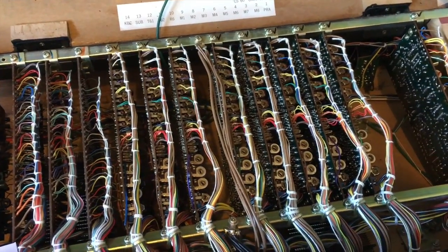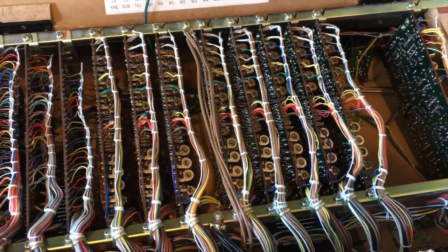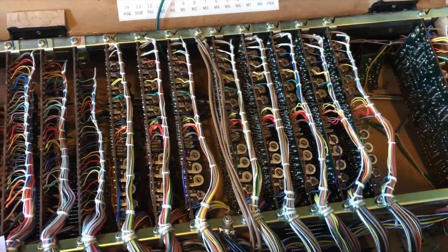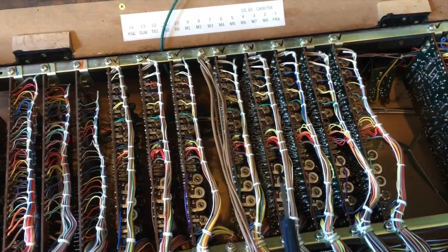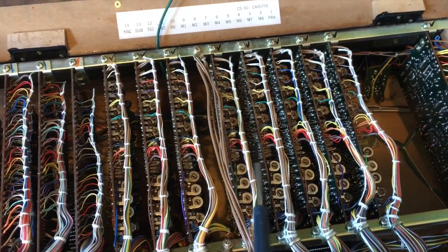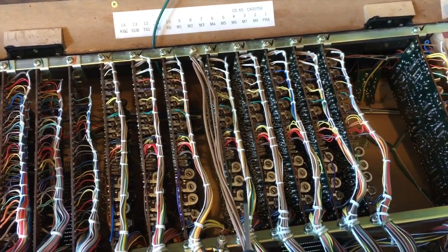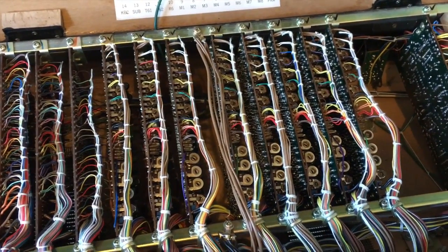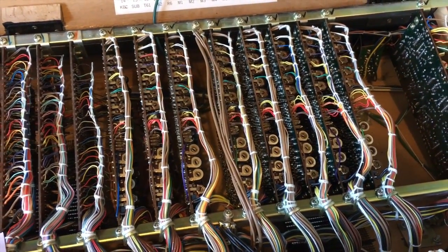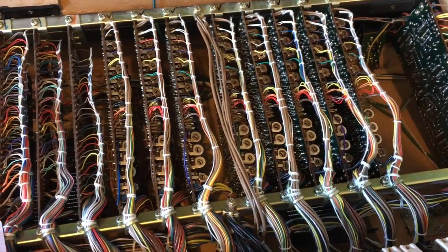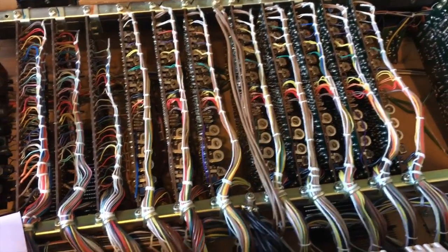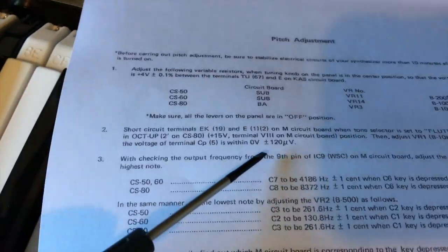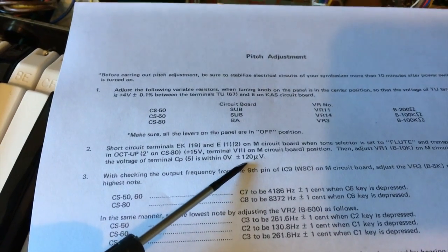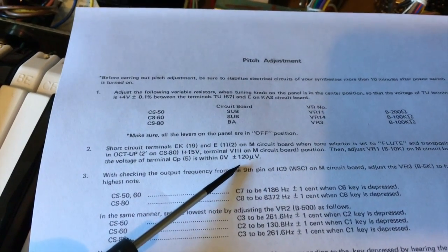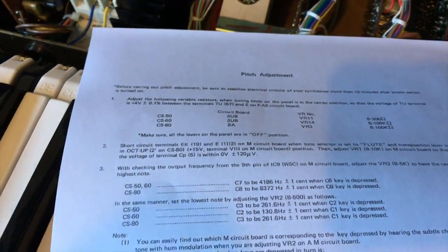So I finished the 0 calibration on the 8 voice cards. Some of them were quite far out. I think voice 5 was 5 millivolts out, and I had a couple that were around about 3 millivolts out. Most of them were between 1 and 2, but to have a few cards that high was quite an issue. They're supposed to be within 120 microvolts, so that's 0.1 millivolt. So to be 5 millivolts out, that's way out.